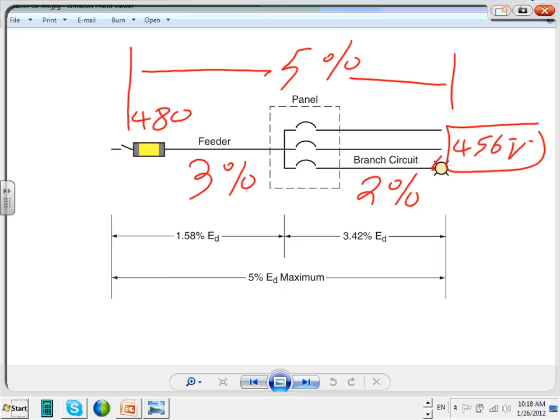It will not function properly, meaning it might not give you the same amount of work. And at a certain level, if you keep reducing until you drop it to 380 volt, smoke starts coming out of it. Well, there will be overcapacity devices that drop, of course. If it's a machine, you will have an overload that drops. But at one point, if there's no protection and you drop it to 380, you will burn your equipment. Because to compensate for the low voltage, what do you think the equipment is going to do? They start sucking more current.